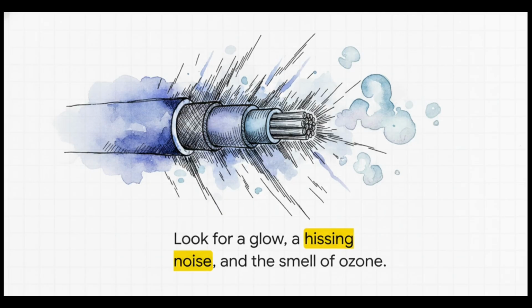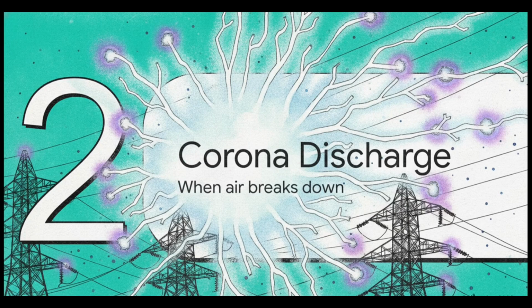If you know exactly what to look for, especially at night, you might spot this faint, luminous, bluish-purple glow wrapping right around the conductors. Along with that hissing or crackling noise, you might even catch a very distinct metallic smell in the air. That's ozone. These are the vivid, real-world symptoms of a grid pushed to its absolute limits. But what is actually happening up in those wires to cause all of this? That brings us to Section 2, the corona discharge glow, or what happens when the air breaks down.